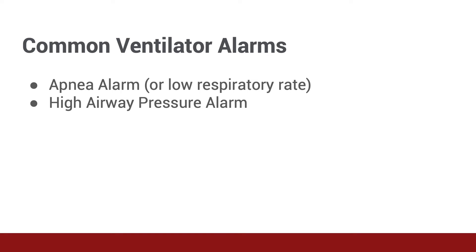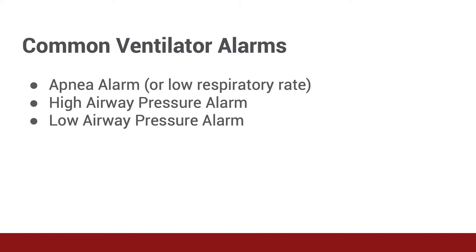Pressure alarms are very important to monitor in the vented patient. Secretions, water in the tubing, or kinks can cause high pressure alarms — suction the patient and look for tube kinking. If that doesn't fix the problem, disconnect the patient from the circuit and manually ventilate with a bag valve. Low pressure alarms can indicate a leak in the system, such as a deflated endotracheal tube balloon or a tubing disconnection. It's important to systematically follow the vent tubing from the machine to the patient to make sure lines are connected and there are no leaks. Alarms can also detect changes in expiratory volumes; decreasing expiratory volumes indicate a leak, similar to low airway pressure alarms.